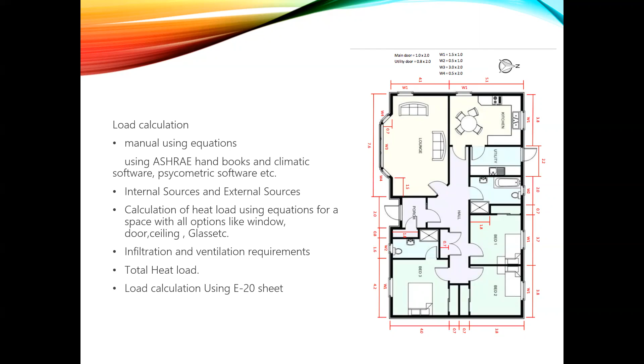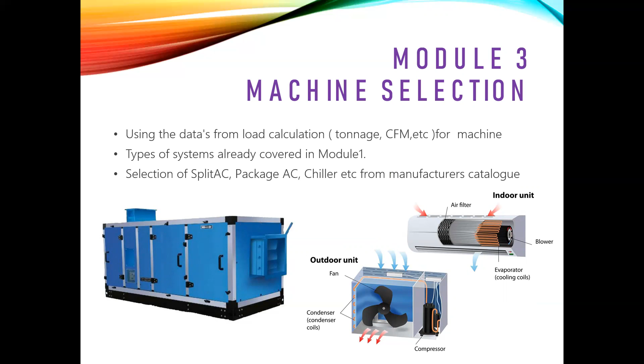So after that, you will have an idea about how we get the heat load. Based on that load, we will be able to select a machine. As you can see, in module 1 we have already discussed all the systems, so after module 1 you will have an idea about all of them. In this module, from the load calculation, you will get the heat load and CFM and data like that. And from that, you can easily select a split AC or package or chiller from the manufacturer. The manufacturers will provide a catalog. From this data, we can select the required machine.